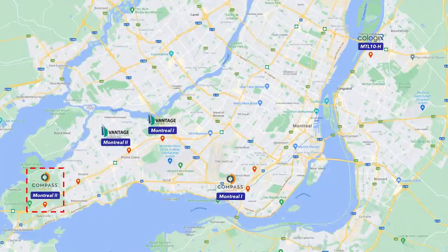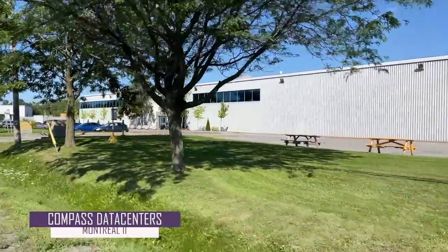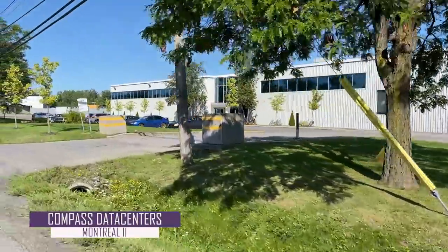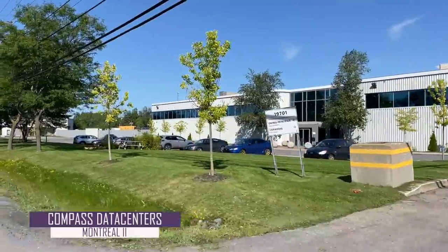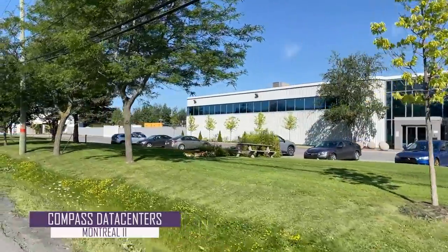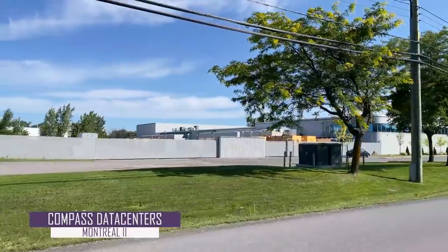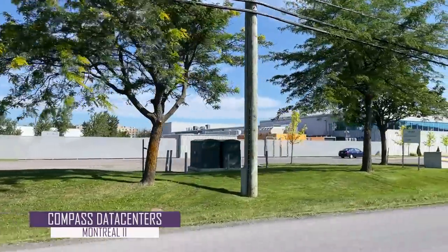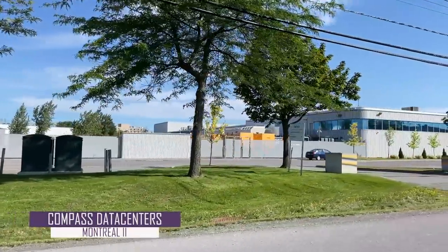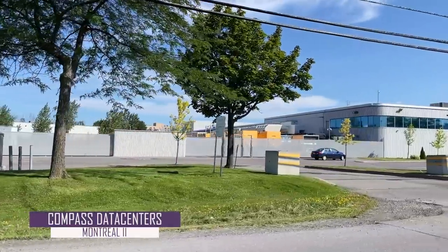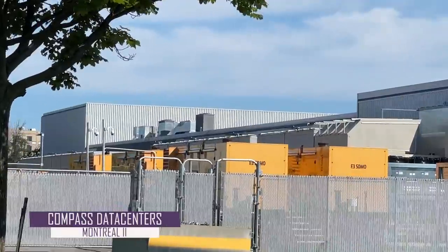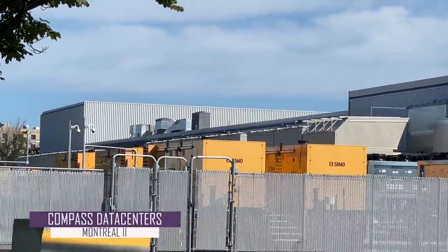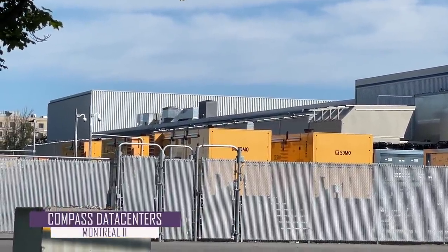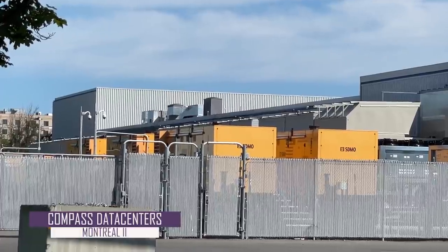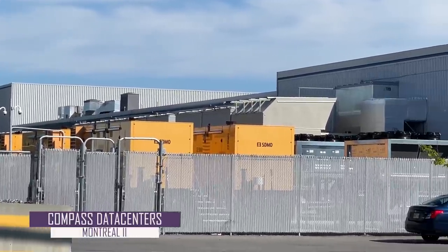Next up is Compass Data Center's Montreal 2 facility. At 175,000 square feet, Compass Data Center's Montreal 2 campus offers 30 megawatts of capacity over 9 available data halls. The site is located on 384,000 square feet of land with the potential for 50 megawatts of power capacity on site. As we zoom in, you can see similar diesel generators once again from SDMO. This data center has 18 of these generators, with each having about 1 megawatt of power capacity.